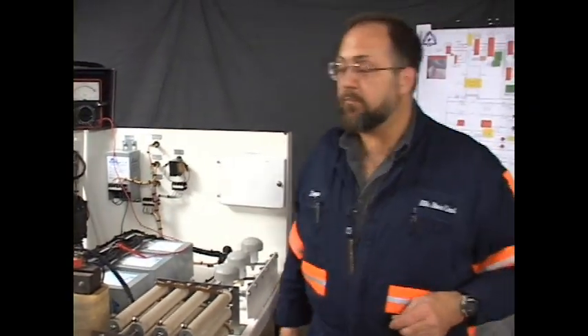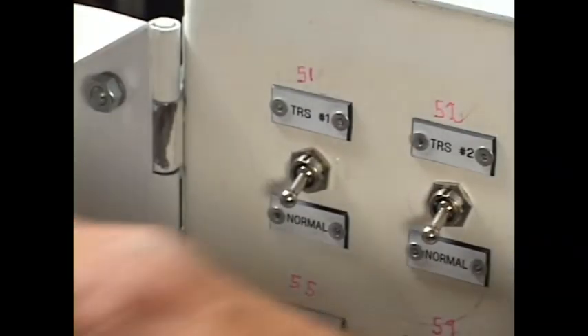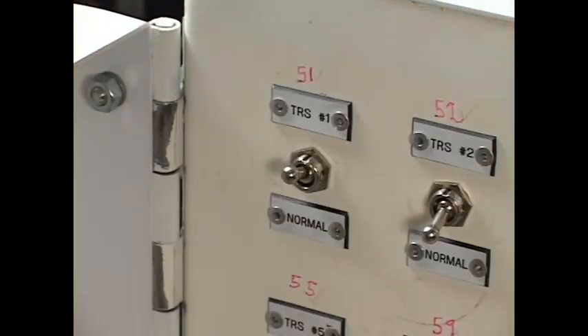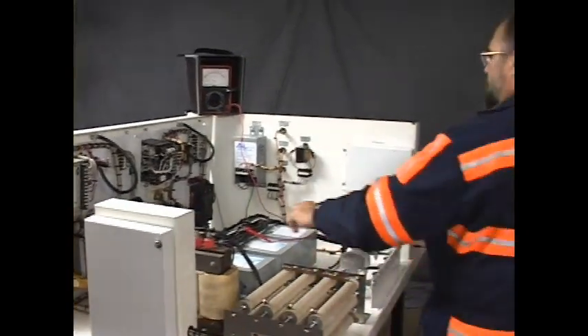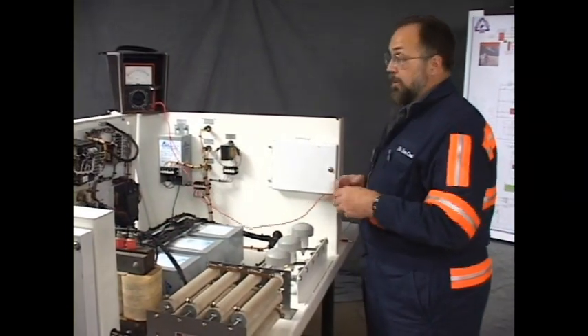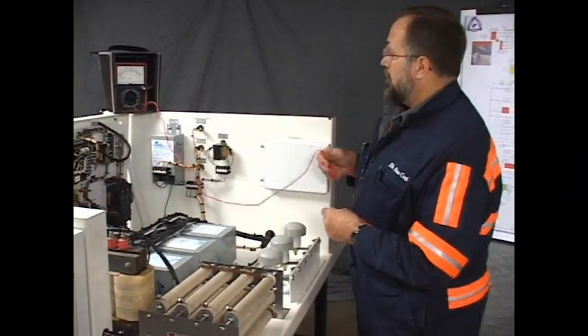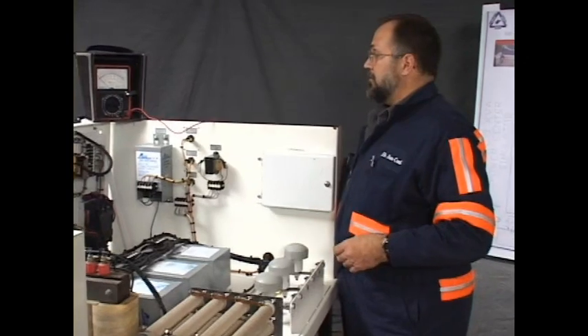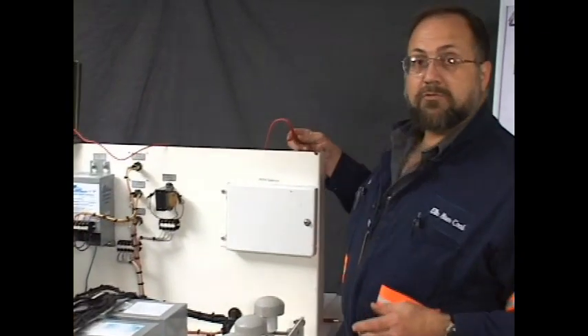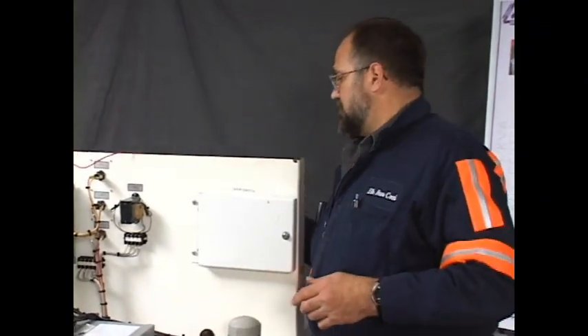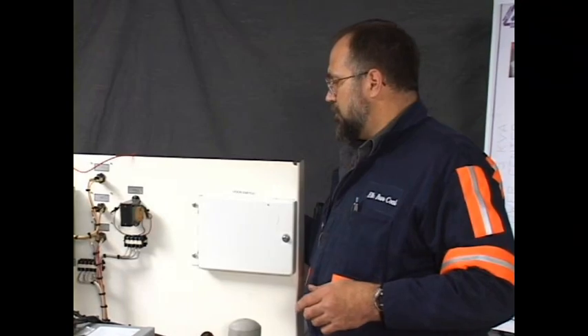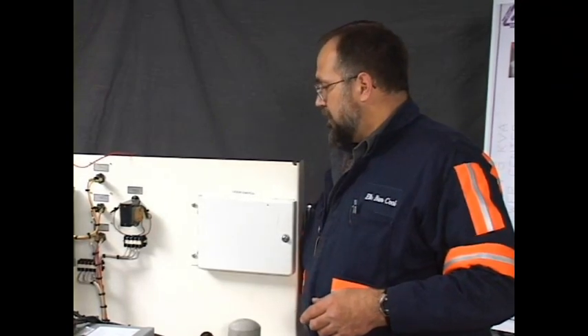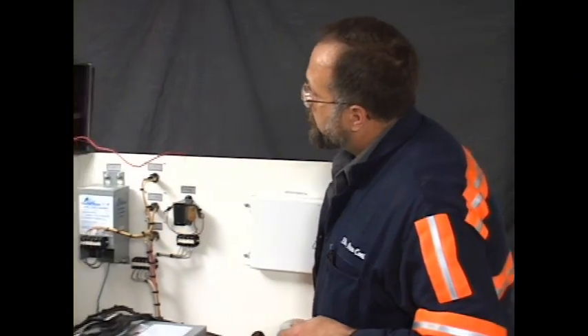Now we're going to install the problem by operating this toggle switch, 51, and do the same checks again with the problem installed. Now, again, you always zero your instrument to start to give you the most accurate reading possible. And I'm going to attach my two probes together. The instrument is 0.